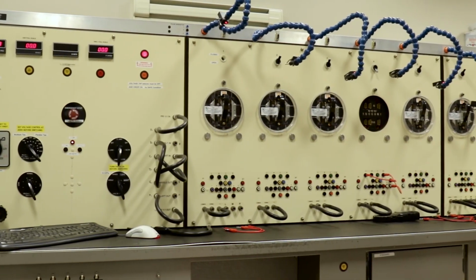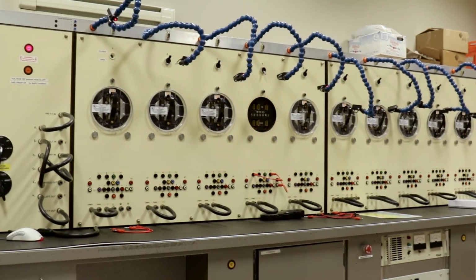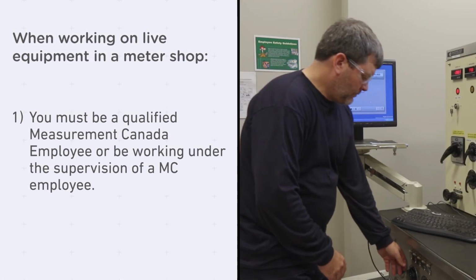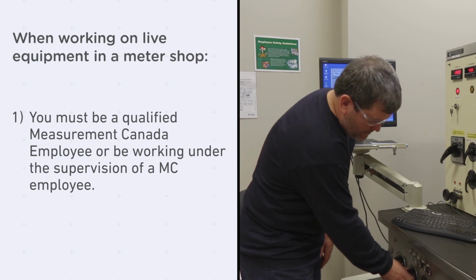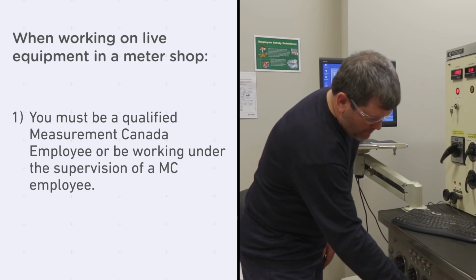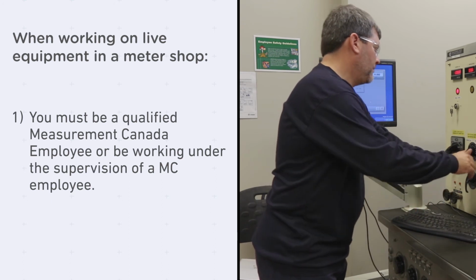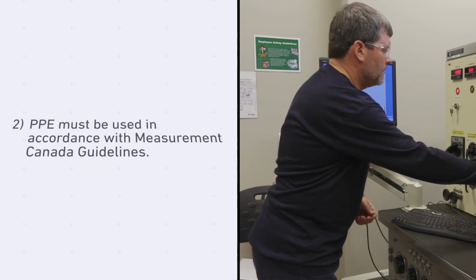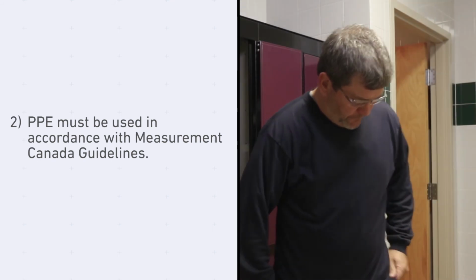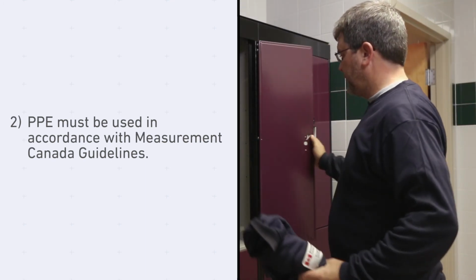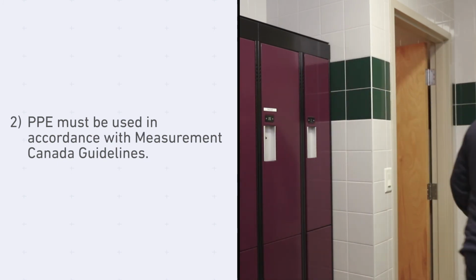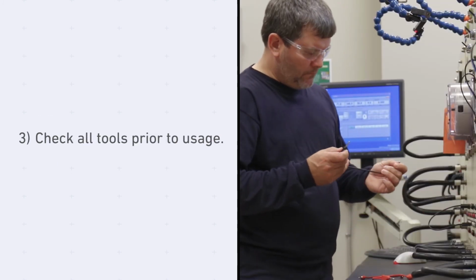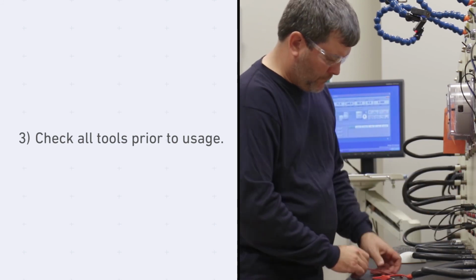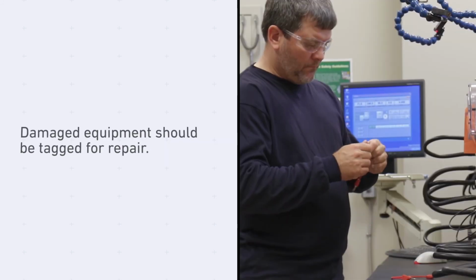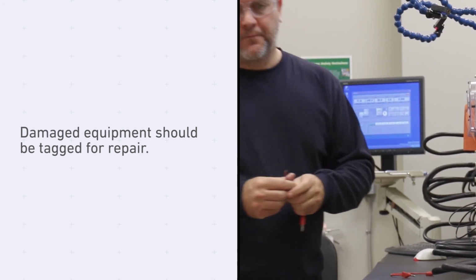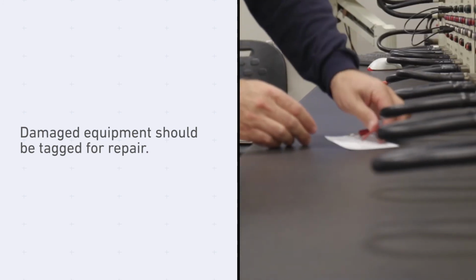When working with live equipment in a meter shop, the following procedures should be employed. 1. Only qualified employees or persons working under the direct supervision of a qualified Measurement Canada employee shall be permitted to work on or near electrical equipment. 2. Personal protective equipment shall be selected, inspected, and used appropriately, as per Measurement Canada procedures. 3. All tools and equipment shall be checked for safety, applicability, and appropriate rating prior to usage. Defective, worn, or damaged equipment shall be tagged and not used until repaired.